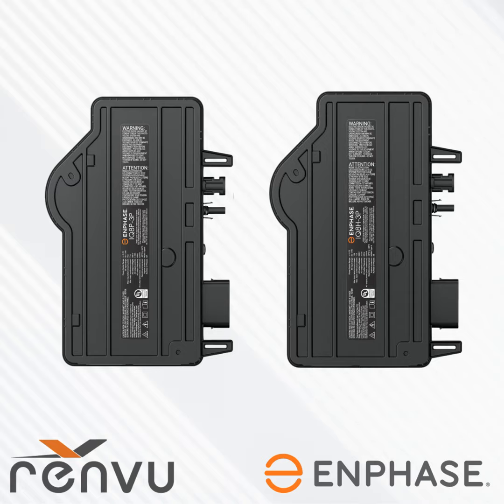So here's just a quick graphic of what that's going to look like. You'll see, in a fully loaded branch circuit of 12, you'll have 6 micros on one side, 6 micros on the other side, center tap adapter in the middle, and that's where you'll run it from. You'll have terminator caps on either side of that circuit. It's not that hard, but it's just something to know about the product. Now, depending on which drop you start from, this center tap plug is going to move around the circuit. So if I'm starting from drop number 2 instead of drop number 1, the center tap plug will be here. No big deal. Just always use the center tap plug that's closest to the middle of the circuit.